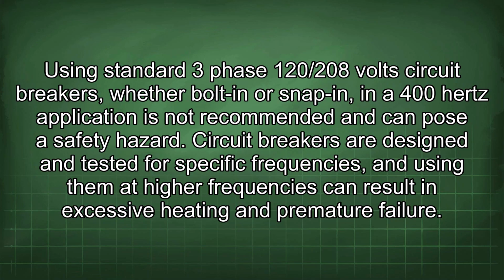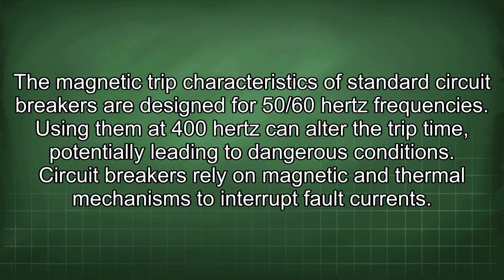Using standard 3-phase 120/208 volt circuit breakers, whether bolt-in or snap-in, in a 400 Hz application is not recommended and can pose a safety hazard. Circuit breakers are designed and tested for specific frequencies, and using them at higher frequencies can result in excessive heating and premature failure. The magnetic trip characteristics of standard circuit breakers are designed for 50/60 Hz frequencies. Using them at 400 Hz can alter the trip time, potentially leading to dangerous conditions.